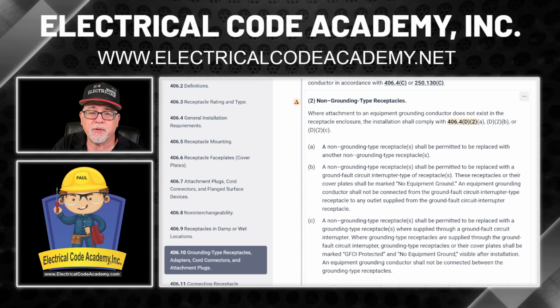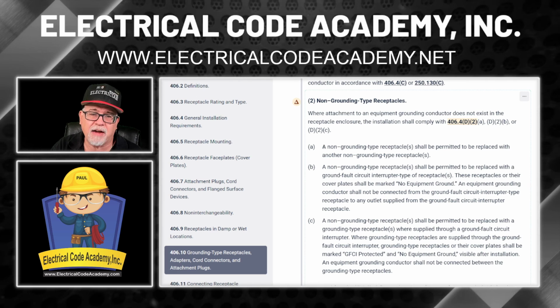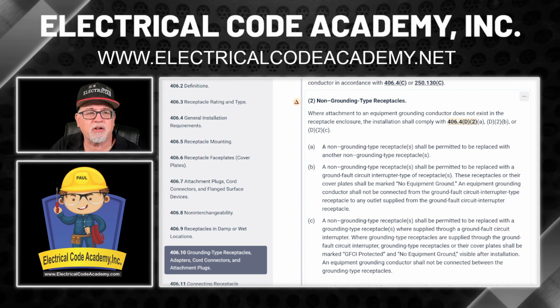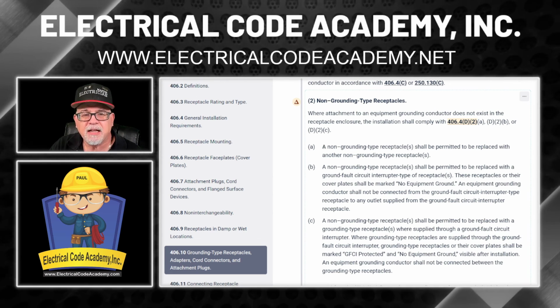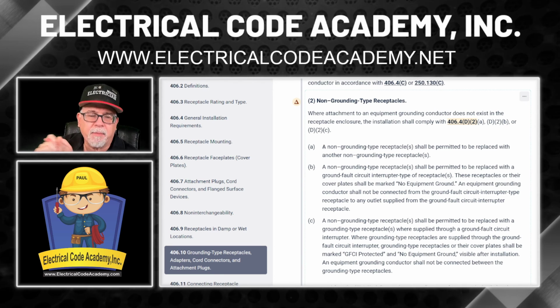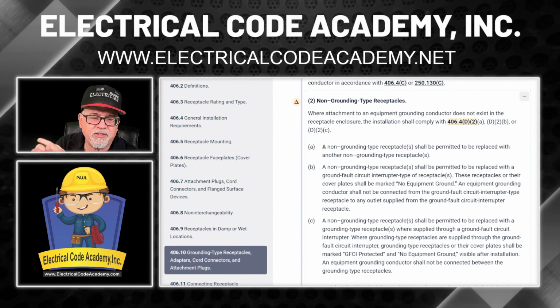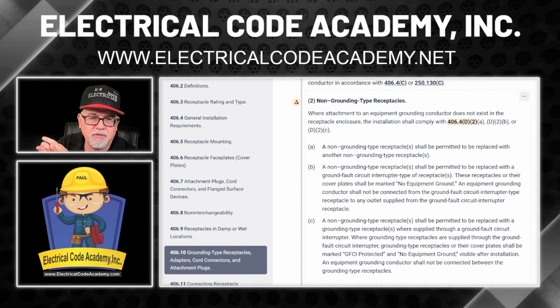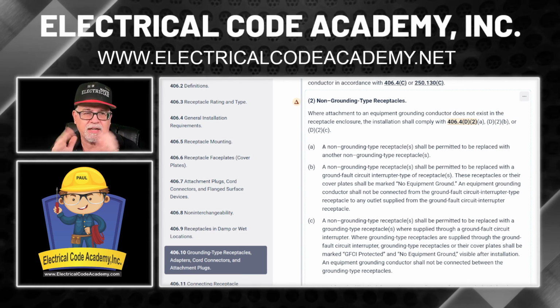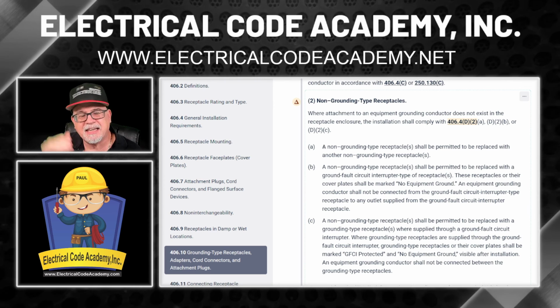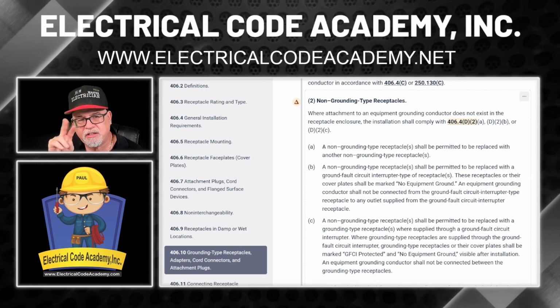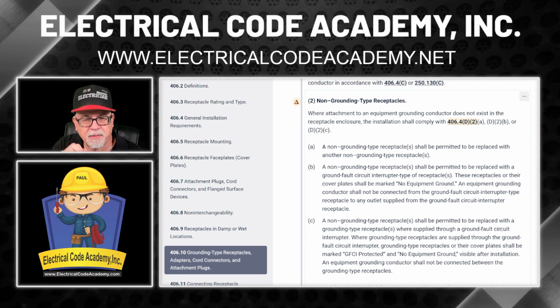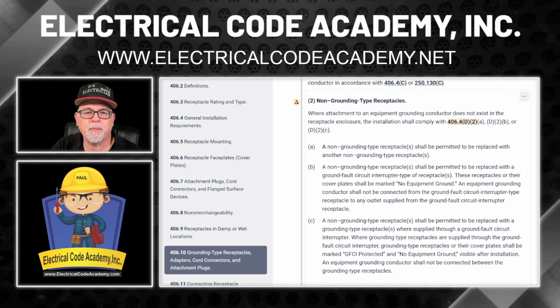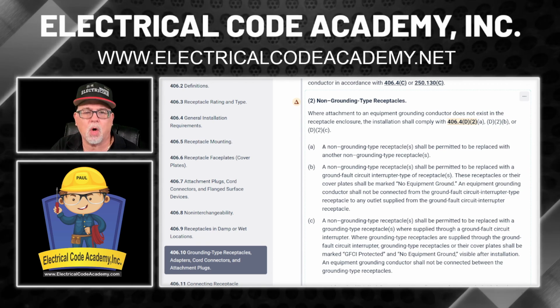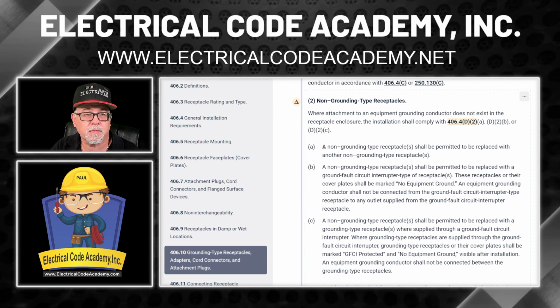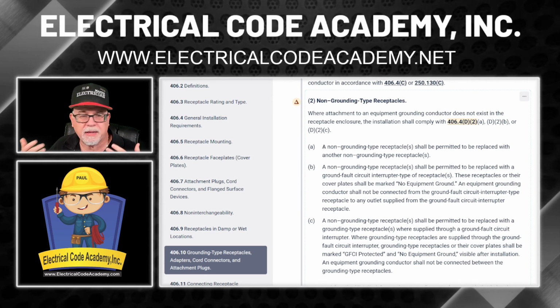But instead of just putting a label on there that says no equipment ground, on all those receptacles that are supplied from the GFCI device, they have to have GFCI protected put on them, and they also have a label that says no equipment ground, just like the one if you just put a single receptacle in like he did. So if you're going to be protecting any downstream from that device, then it's going to need two labels on it. One that says GFCI protected, one that says no equipment ground, okay? And they have to be visible on the actual cover plate or the device, okay? So typically, that's what you'll see.